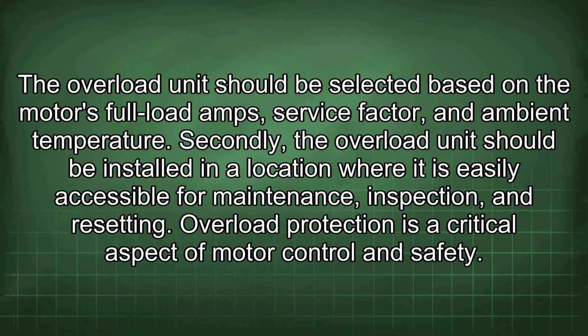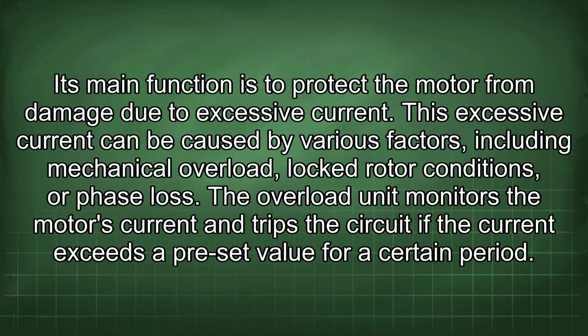Overload protection is a critical aspect of motor control and safety. Its main function is to protect the motor from damage due to excessive current. This excessive current can be caused by various factors, including mechanical overload, locked rotor conditions, or phase loss. The overload unit monitors the motor's current and trips the circuit if the current exceeds a preset value for a certain period.